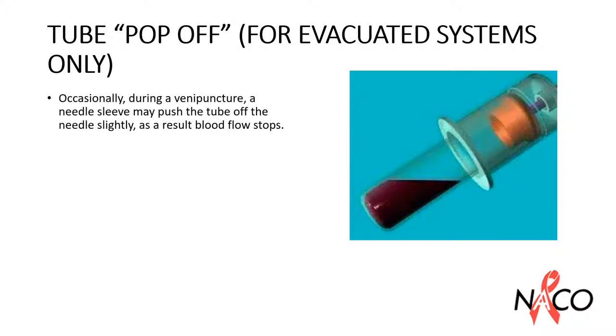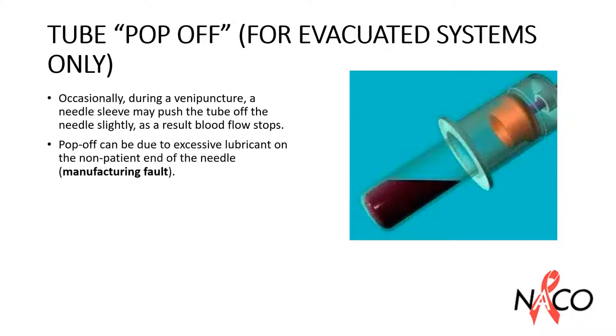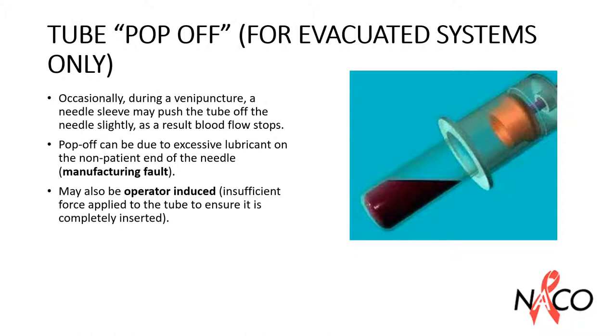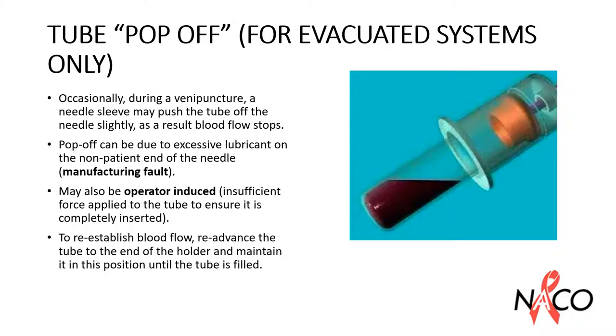Occasionally during a venipuncture, a needle sleeve may push the tube off the needle slightly, as a result of which blood flow stops. Pop-off can be due to excessive lubricant on the non-patient end of the needle — a manufacturing fault — or a faulty MSN sleeve, also a manufacturing issue. It may also be due to the operator applying insufficient force to the tube to ensure it is completely inserted onto the non-patient needle. To re-establish blood flow, re-advance the tube to the end of the holder and maintain it in this position until the tube is filled.